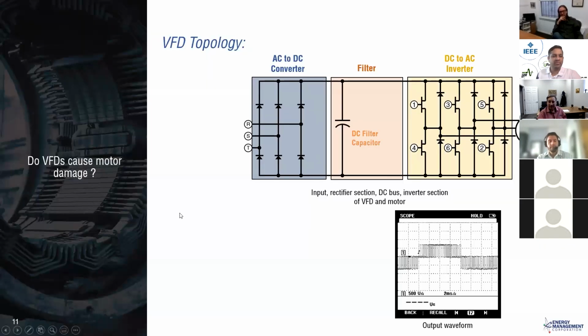So let's move on. To understand the issues, and particularly those that Mr. Matsuda posed, we're going to start with the output section of the VFD. A VFD typically, when you look at the topology, consists of a converter section, a DC bus filter capacitor section with control. And then the output is an inverter, inverting DC to AC. The typical waveform is what you see here at the bottom. It's a typical PWM waveform, where the longer the pulse is on, the more voltage is going to be seen by the motor, and it's going to synthesize an AC sine wave from a current standpoint.